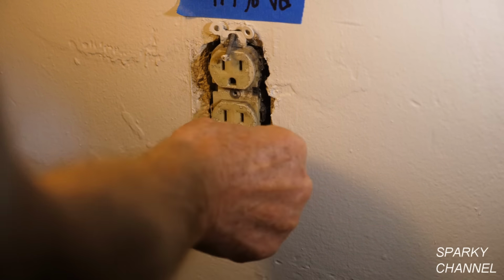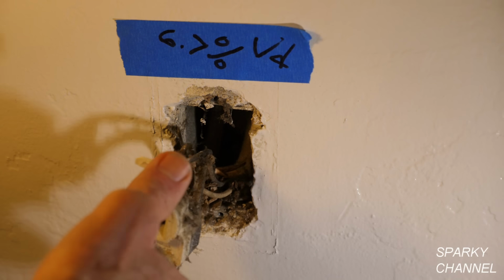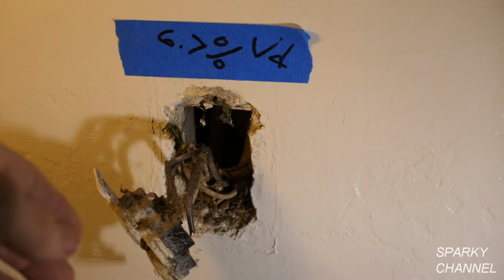I'll move to the second receptacle. After double checking the outlet, I'll spin off both of the old flathead screws and pull out the old 2-prong receptacle. This outlet is what we call a backstab receptacle. I'll use my diagonal cutters and cut the wires flush with the back of the outlet. After I cut the wires flush, I'll strip new ends on them. This is what the old 2-prong outlet looks like once you've cut the wires. Now I'll vacuum out this box. I'll repeat this procedure for the other 5 outlets on the circuit.